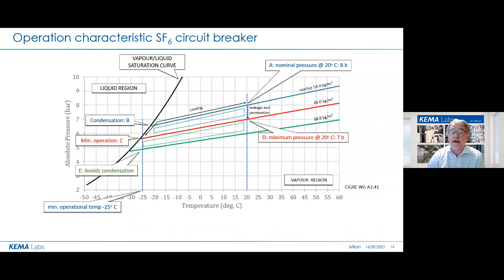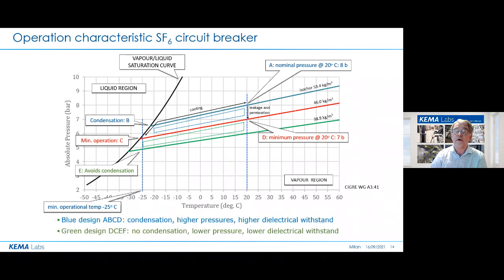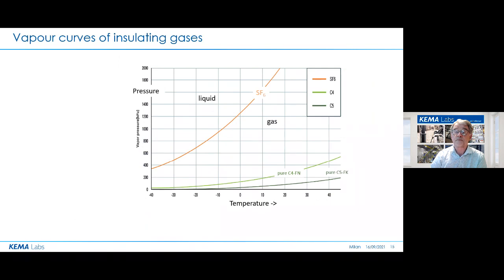The blue track at higher pressure, allowing condensation, and on the safe side dielectrically, or the green track, which has a lower operating pressure, no condensation, but less margin from a dielectrical point of view. So this is again for SF6. So let us now compare the new gases with SF6.